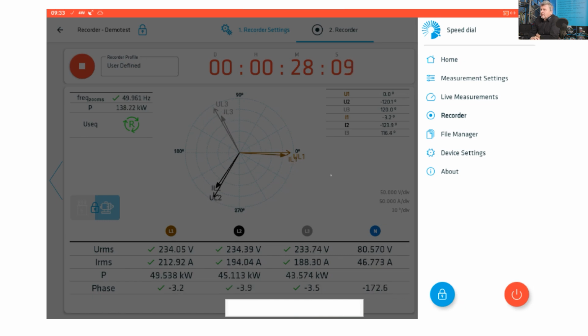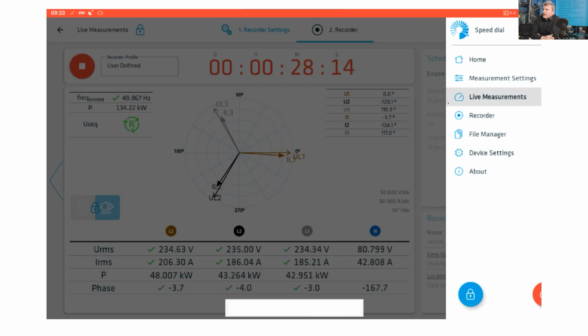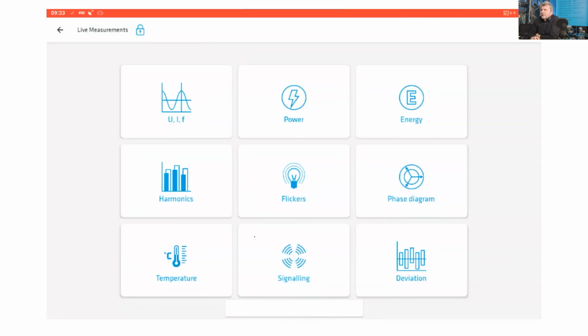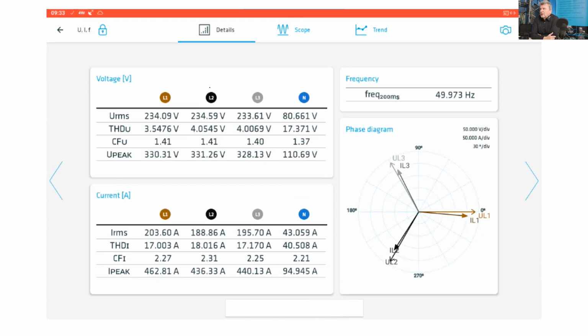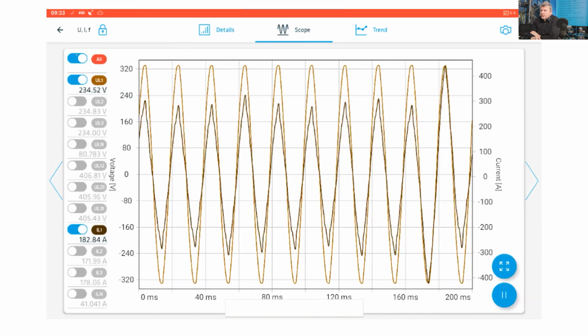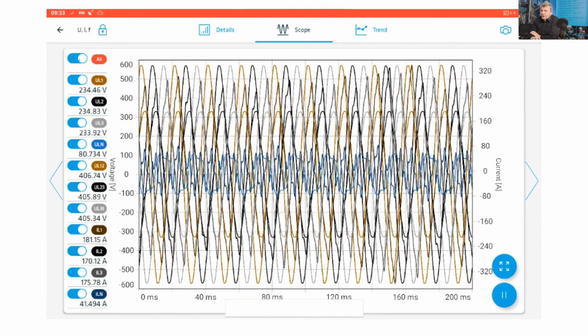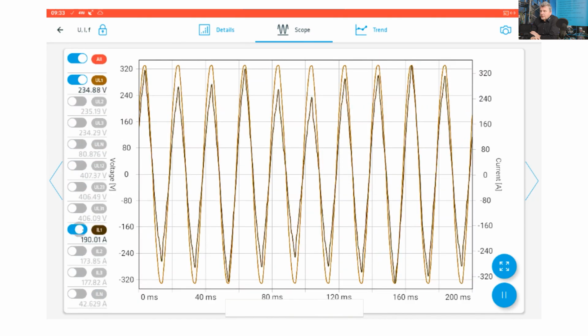As already mentioned, we provide the recorder screen. Then we have the live measurement screen, which is divided into 9 different functionalities: voltage, current, power, energy, phase diagram, flicker, harmonics, and so on. If we look deeper inside the voltage current screen, the operation is similar for all of them. Voltage current frequency will present the main information about voltage, current and phase diagram. Later, with the scope view, you can monitor each of the voltages and currents.